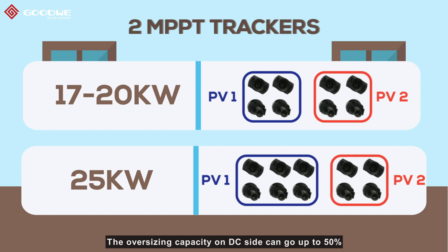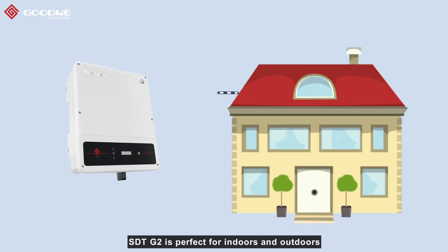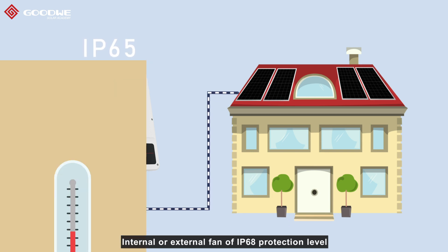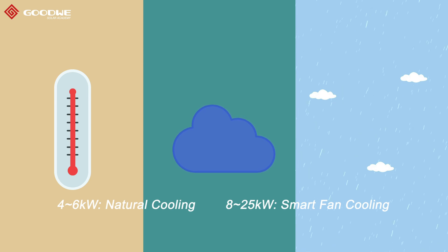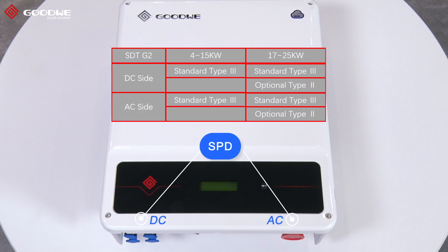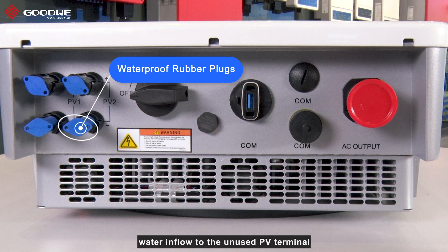The oversizing capacity on the DC side can go up to 50% and the overloading capacity on the AC side can go up to 10% in constant mode. The SDT G2 is suitable for both indoor and outdoor installation with overall IP65 protection. An internal or external fan with IP68 protection keeps the inverter cool in harsh environments. Besides all necessary protections, SDT G2 has integrated SPD on both DC and AC sides, and there are waterproof rubber plugs to prevent water inflow to unused PV terminals.